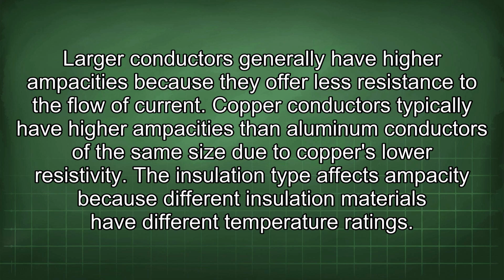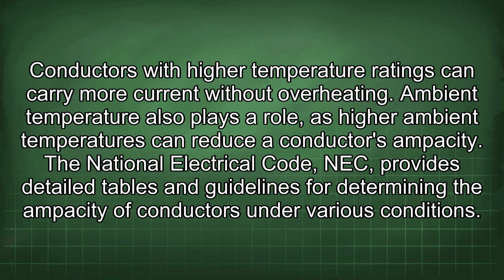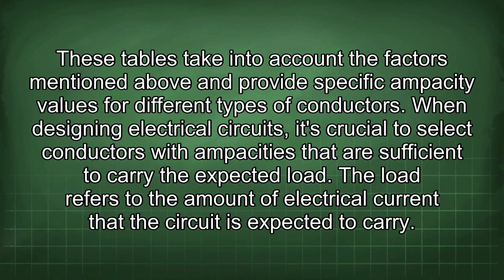The insulation type affects ampacity because different insulation materials have different temperature ratings. Conductors with higher temperature ratings can carry more current without overheating. Ambient temperature also plays a role, as higher ambient temperatures can reduce a conductor's ampacity. The National Electrical Code (NEC) provides detailed tables and guidelines for determining the ampacity of conductors under various conditions. These tables take into account the factors mentioned above and provide specific ampacity values for different types of conductors.